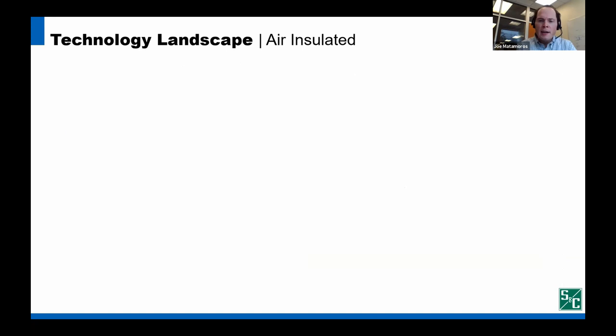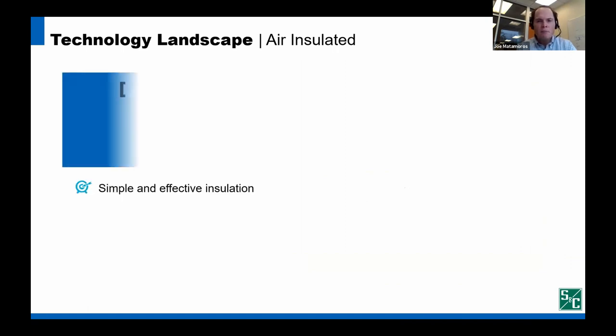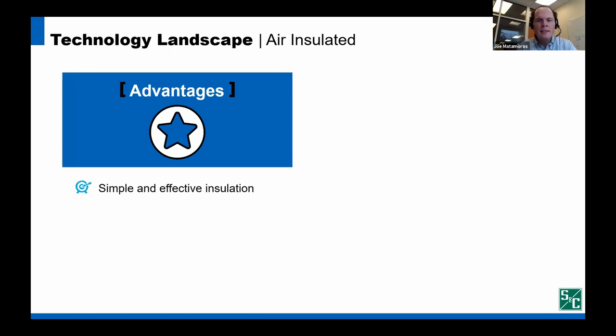As I mentioned, air insulated gear, and as shown in the poll results, is the most widely used technology. And there are two reasons for its ubiquity. One, it was the earliest technology available. And two, it still has several advantages today versus other technologies. The first advantage is that air is simple and effective. There's no need to evaluate the state of health of air insulation. The operator can see the live parts and the state of the gear.